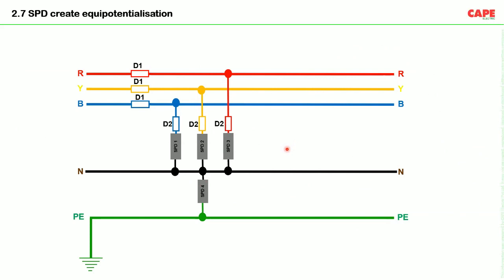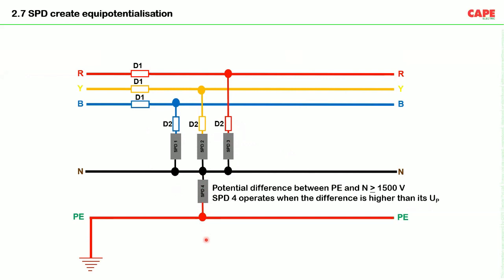In this combination, imagine there is a lightning strike. Lightning strike is creating a high potential on the earth, for example. So the earth potential is going up. How does this device operate? Imagine I have 4 spark gap based SPDs with a voltage protection level of 1.5 kV. It means once the potential difference between the PE terminal and the neutral terminal is more than 1.5 kV, this device acts like a switch. Now, imagine the voltage is more and this device has acted like a switch. As a result, your earth and the neutral are shorted. Actually, it is not 100% shorted, but you just imagine that it is shorted.